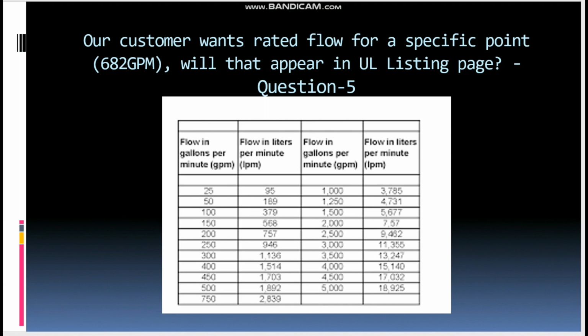Okay, this is for the fire pump. The answer is, normally in the UL listing there is no specific rule like it will be 682 GPM or 742 GPM or 612 GPM. They have the standard listing, like you see here: 25, 50, 100, 150. So you have to choose the next higher one. For example, if I have 682 GPM, the next one is like 700 GPM. If you see here, 750 GPM or 500 GPM. Our figure falls between these two, and the next higher is 750 GPM, so I need to go with the higher one only. So there is no specific point in the UL listing.